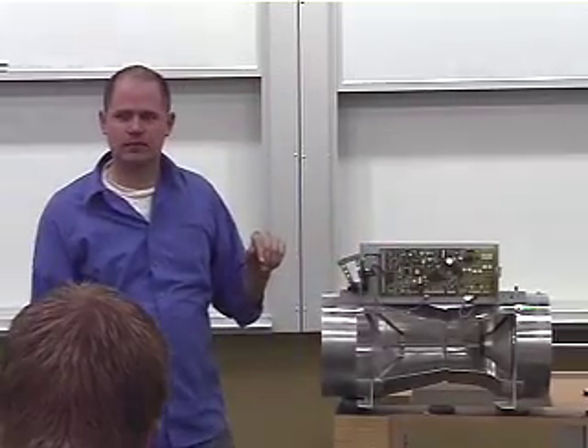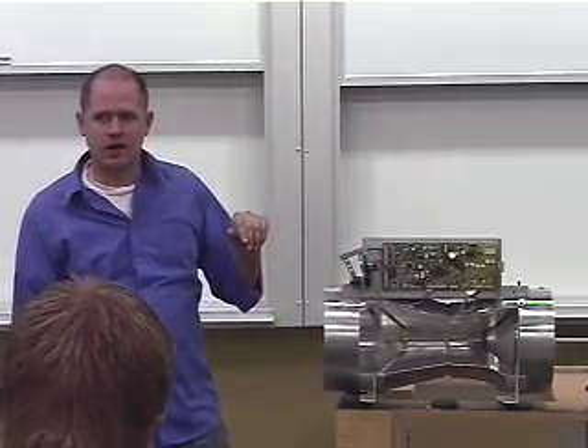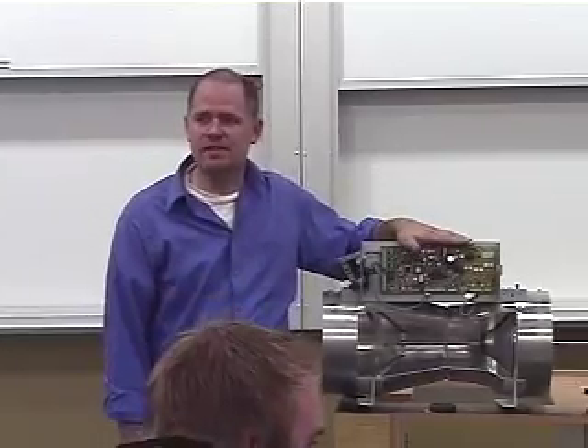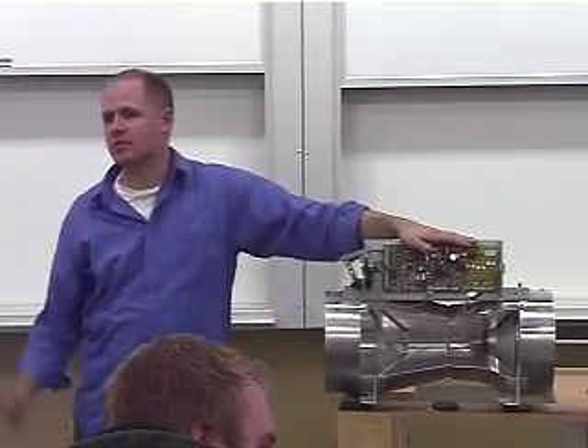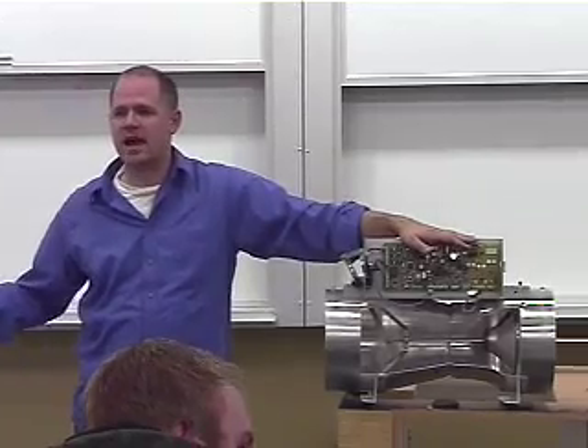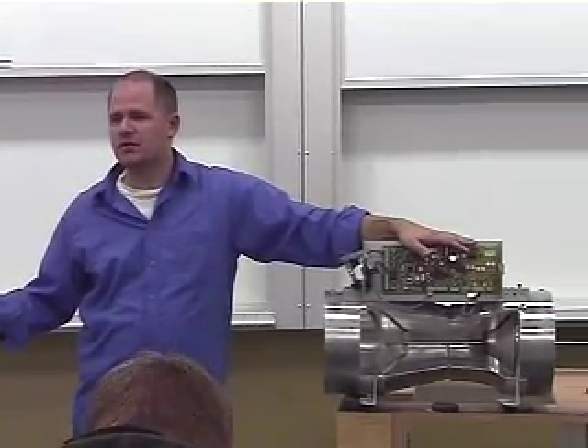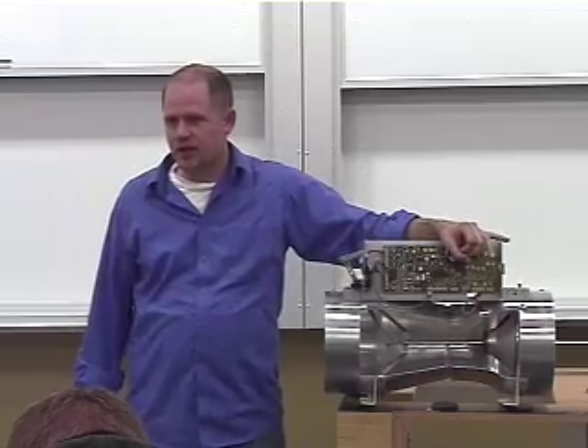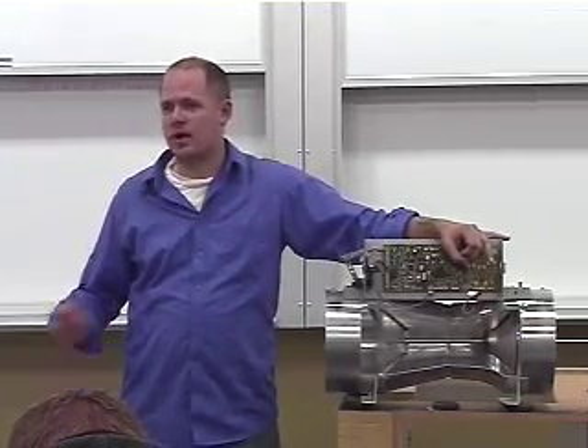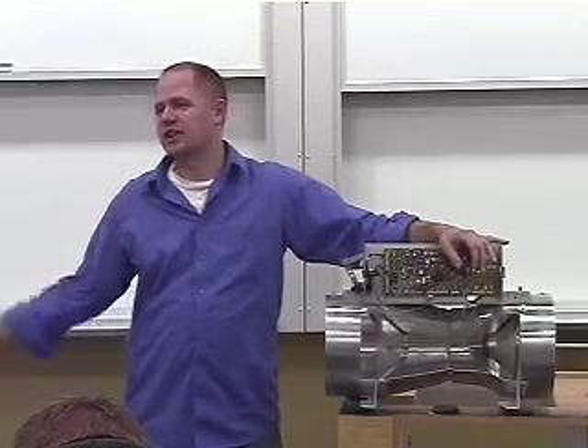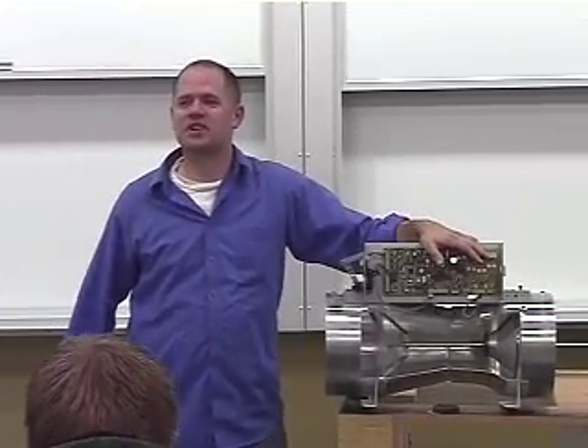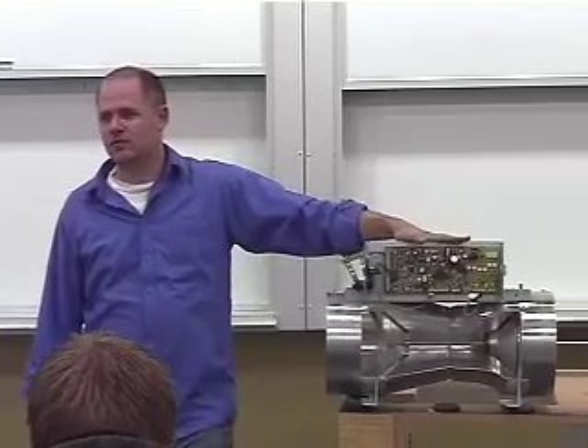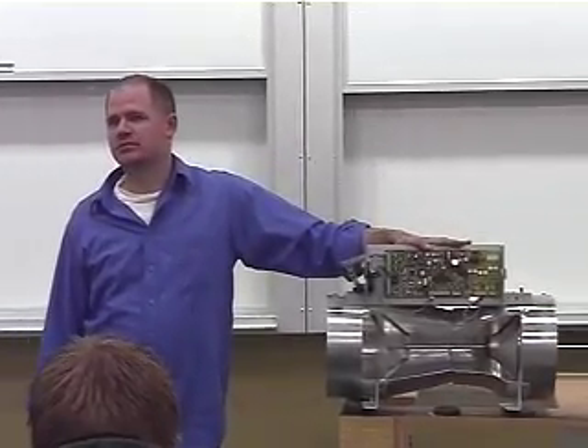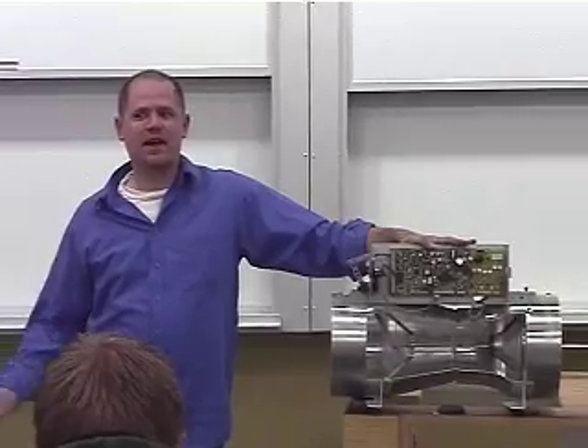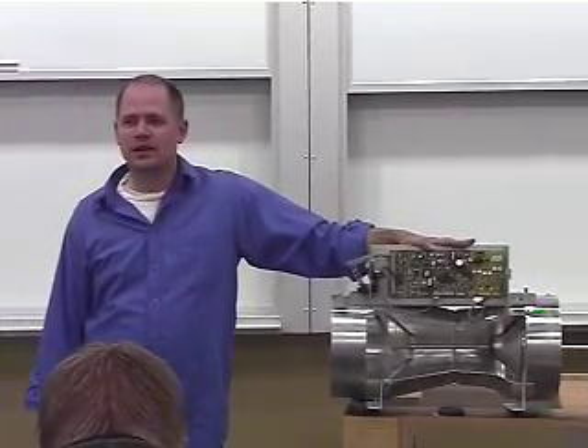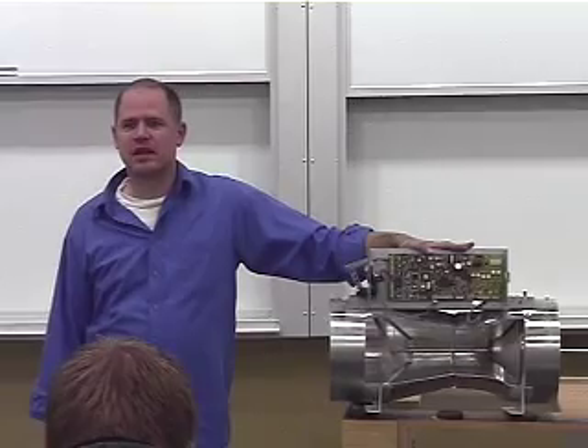Does that circuit board have a reset button on it? There's no resets on these. Typically, to reset the card, you actually unplug power from it, turn the power off, wait till all the lights turn off, turn it back on. On your high-speed cards with all the capacitors, it can take quite a while for those capacitors to discharge. So usually I'll turn them off and go away for an hour or two and let them discharge and then come back up. But you don't have to reset these unless they have some weird issue that you can't figure out, if you can't communicate with them or whatever. Typically they just sit there and run and everything's happy.